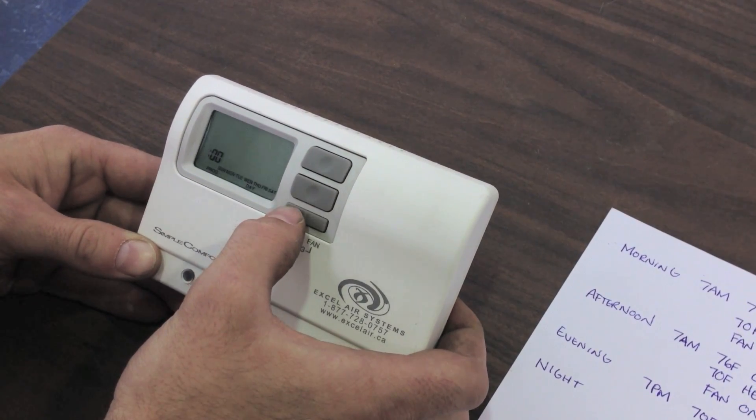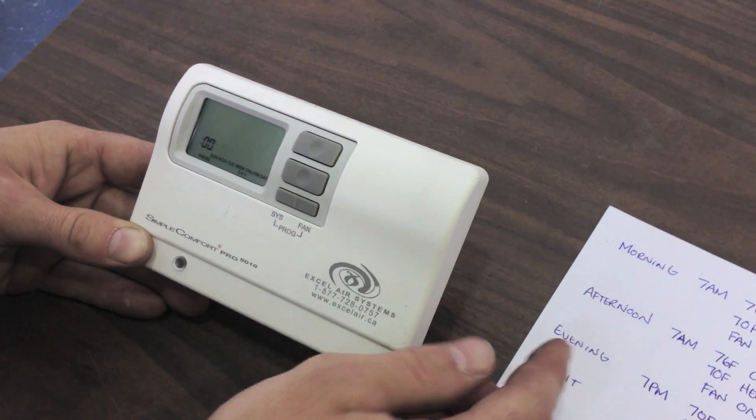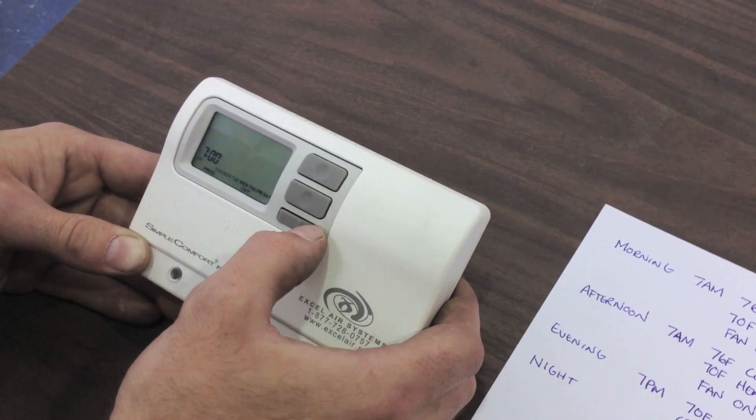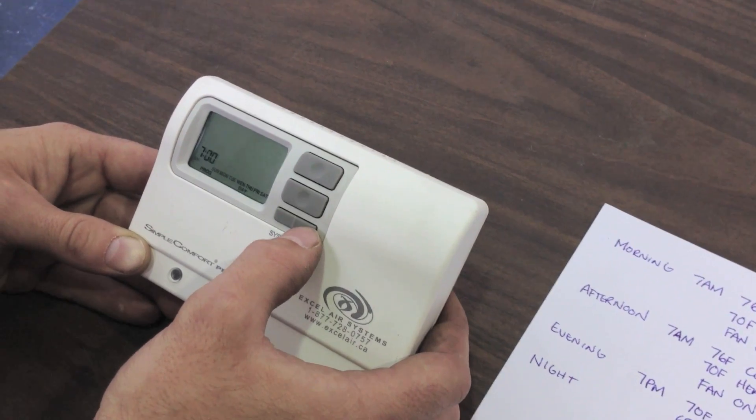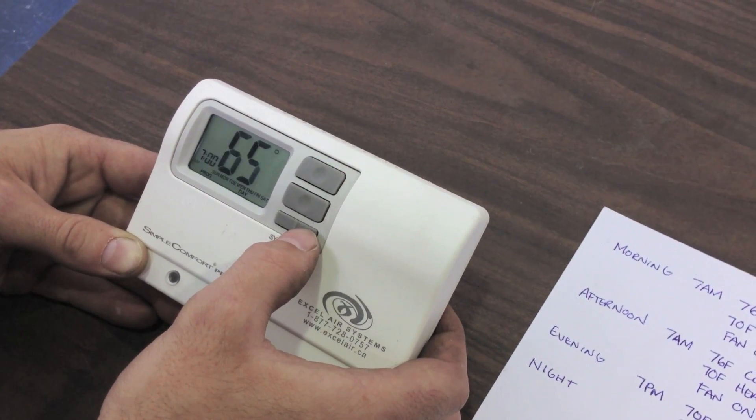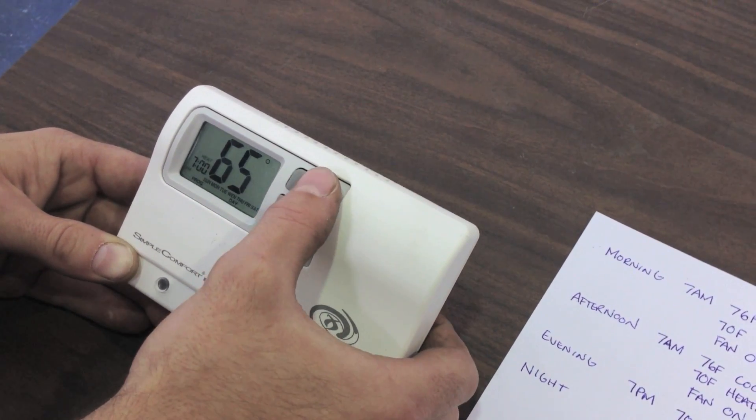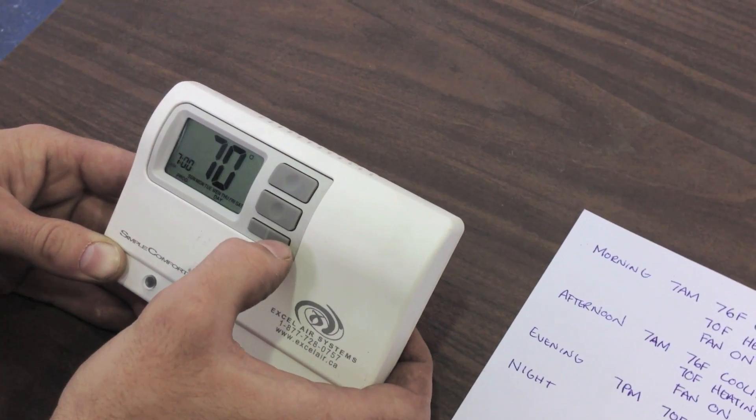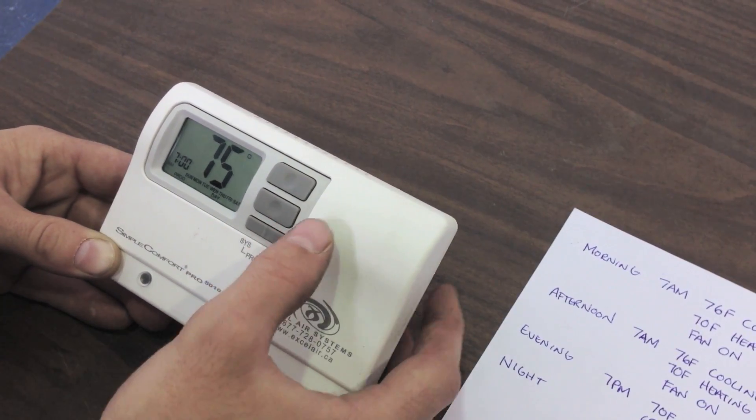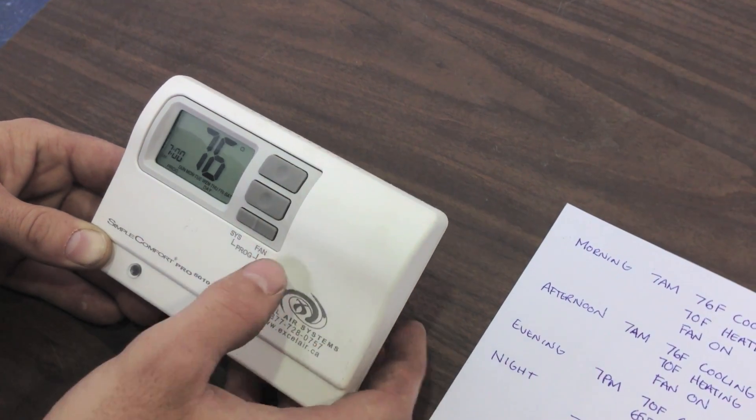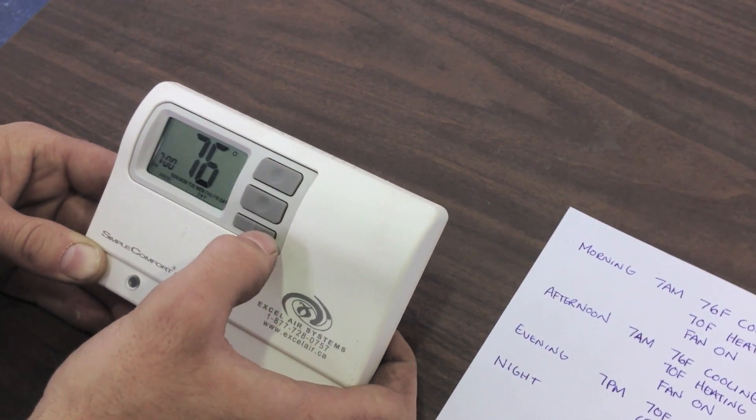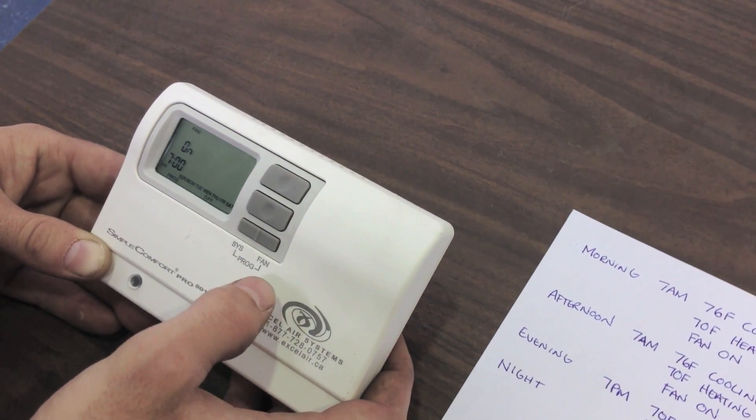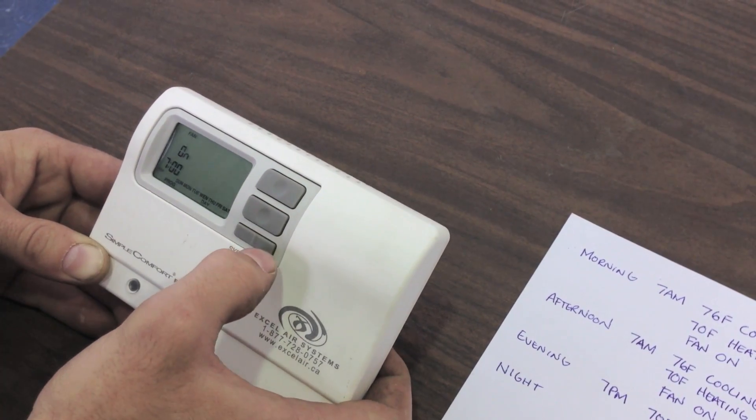So now we have our day schedule showing. So we're going to basically copy the morning schedule by setting it to 7 a.m. We're going to hit fan for next. Our minutes, we're okay. Push fan again. We have our heat set point, which we want it at 70. And then our fan again, which our cool should flash, and we want it for 76. We'll push our fan again. And the word fan is displayed with the on symbol, which is what we want. Push fan again.